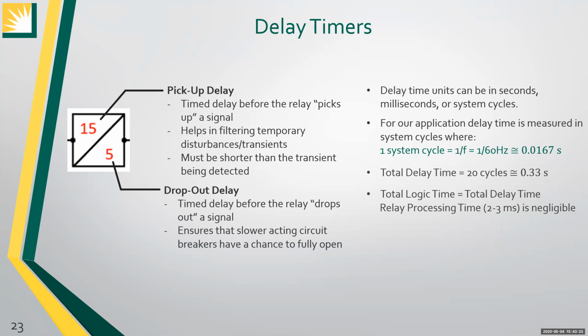Our total delay time for the detection logic is 20 cycles, which falls within a 30-cycle detection window limit and leaves 10 cycles of breathing room for future adjustments and refinement.